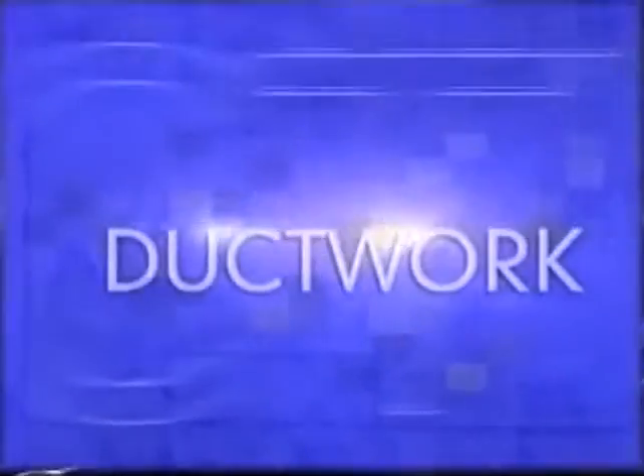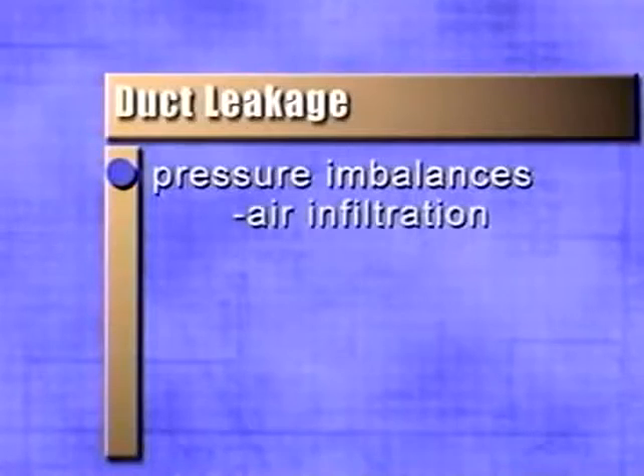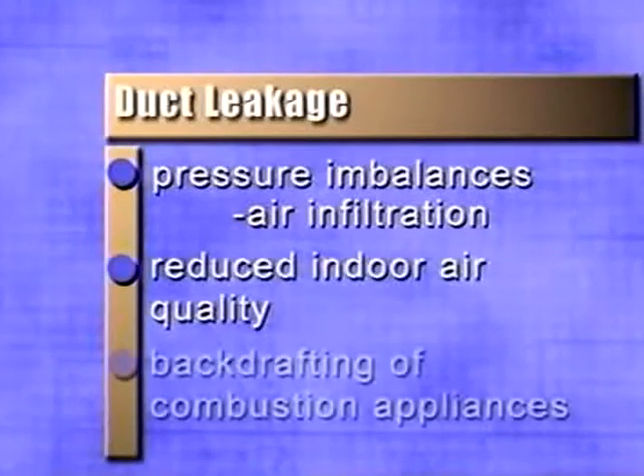Proper installation of ductwork is key to conserving energy and increasing comfort in a home. Sealing ductwork is a major part of a proper installation. Duct leakage can cause a number of problems, including pressure imbalances, which can cause air infiltration, reduced indoor air quality, and even backdrafting of combustion appliances. If ductwork is not sealed properly, the air we've spent money to heat or cool never makes it into the living space. It's estimated that in the average house, we lose from 15 to 25% of heating and cooling energy because of leaks in the ductwork. That's 15 to 25 cents for every dollar we spend wasted.